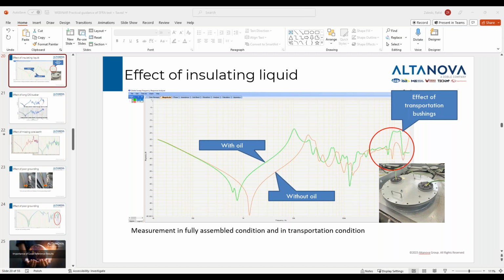Okay, when testing in an electrical substation, due to induction from neighboring electrical lines, sometimes the curves are wrong compared to previous tests. Even the magnetization in the magnetic circuit doesn't allow the curves to be identical. What can I do to make the curves right in the field when the neighboring electrical lines can't be turned off? Well, so basically this I would expect to show you some influence on your trace around the 50 Hertz area.